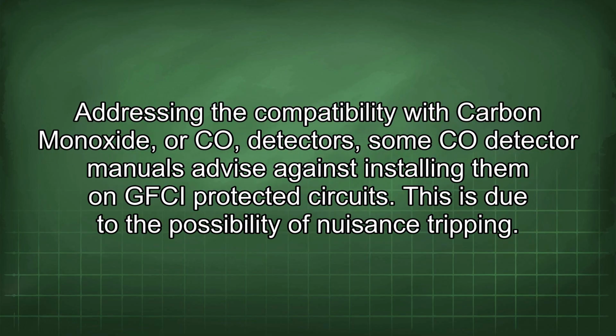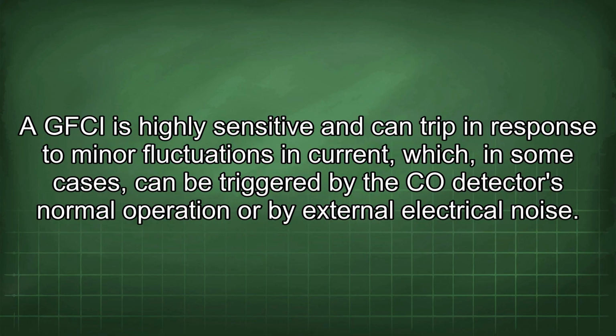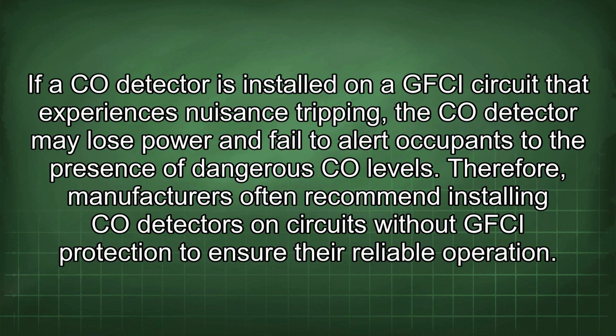Addressing the compatibility with carbon monoxide, or CO, detectors, some CO detector manuals advise against installing them on GFCI-protected circuits. This is due to the possibility of nuisance tripping. A GFCI is highly sensitive and can trip in response to minor fluctuations in current, which, in some cases, can be triggered by the CO detector's normal operation or by external electrical noise. If a CO detector is installed on a GFCI circuit that experiences nuisance tripping, the CO detector may lose power and fail to alert occupants to the presence of dangerous CO levels. Therefore, manufacturers often recommend installing CO detectors on circuits without GFCI protection to ensure their reliable operation.